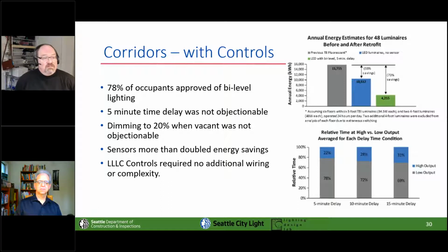A couple of the really key learning things was, we always talk about timeouts for occupancy sensors. Is it 30 minutes? Is it 15 minutes? Is it 5 minutes? Personally, I like 5 minutes. I like short timeouts, and that's frankly because the reason that we used to use 30 minutes had everything to do with the lifespan of fluorescent lamps, which we don't have to worry about anymore. So if you're going to use 5 minutes, you're going to use 15 minutes, whatever that happens to be, they didn't mind the dimming to 20% when nobody was there. So you walk out of your apartment, you're not in darkness, you're at 20% light output.